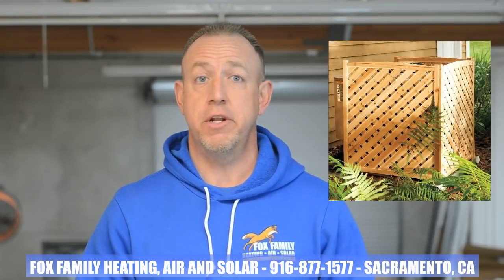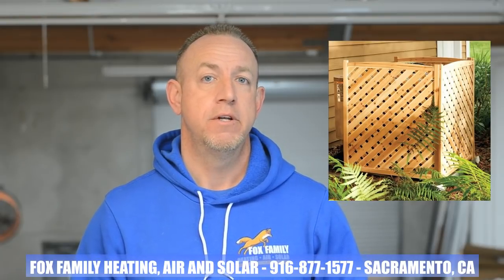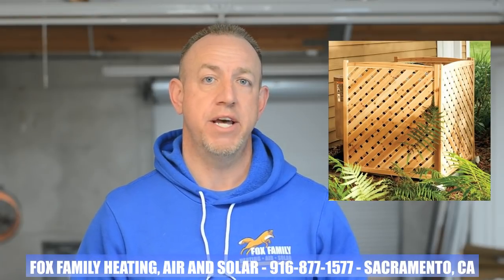Outside at the AC, just make sure you have a 30x30 area in front of your access panel. This way future techs will be able to get in there and make the necessary repairs to get the customer up and going again. And if your homeowner is going to build that lattice structure around the AC, ask them to build it so that it can be slid out and then back in when the AC tech moves on. Don't let them pour concrete piles so that it can securely sit there and never be moved again. That inhibits technicians from doing their job safely.